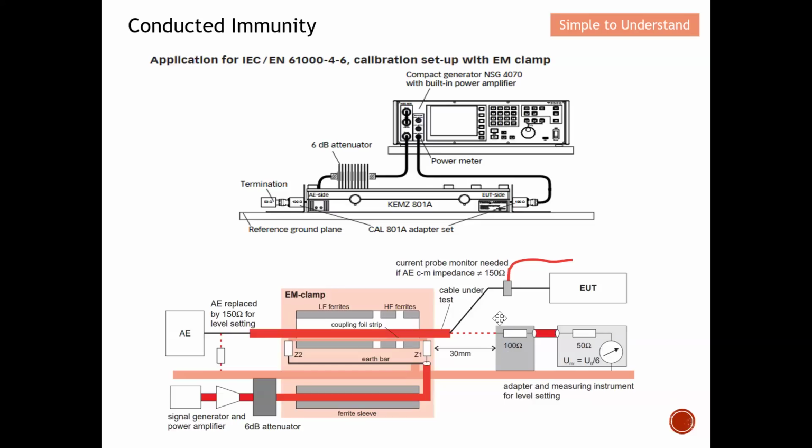On the right, you can see that there are actually two sets of solution. The first set of solution is the EUT. Basically the top one is for the testing of the EUT, while the bottom one is mainly for calibration. When you do this for calibration, it will be routed to this path here. And when you do it for testing, then you will route to this path. So it doesn't mean that these two things exist simultaneously. Either one will appear. For testing it will be this configuration. For calibration it will be this configuration. Okay, let's go through in deep detail here.